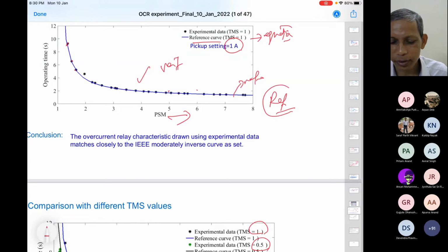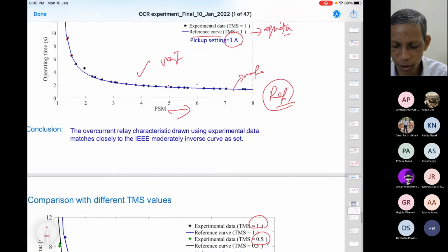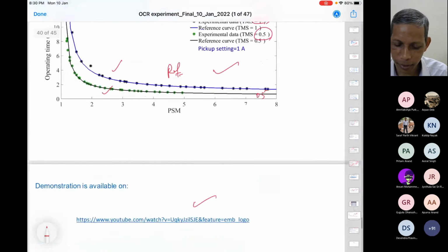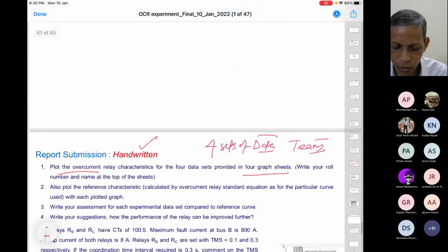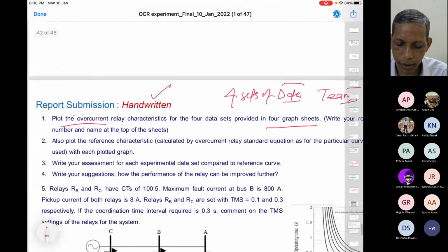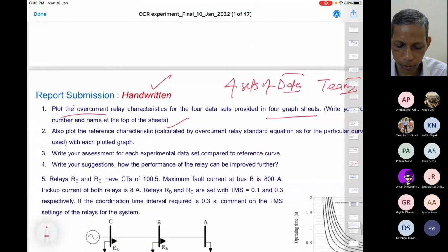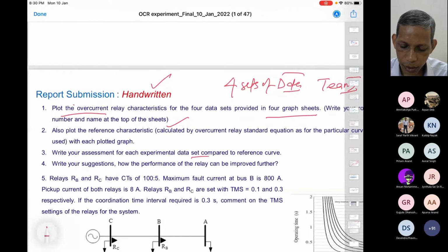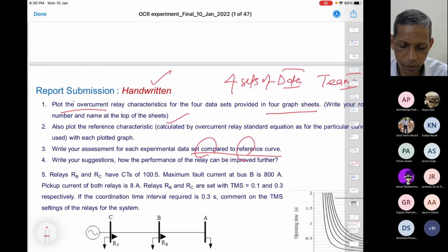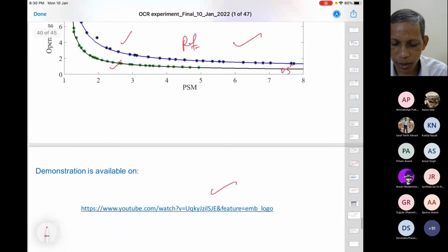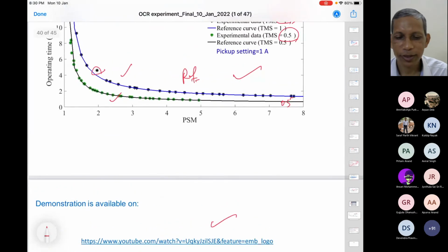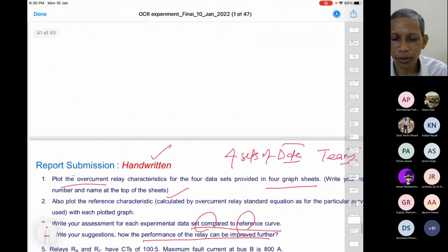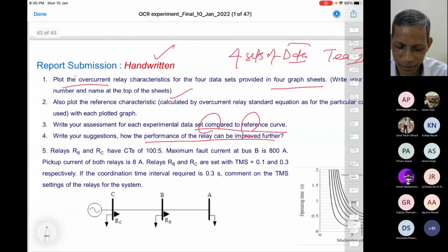Agree? In most of the cases, you'll find that they are following the corresponding curves because the relay is very reliable in that sense. The other one, the reference curve, you have to calculate from that. And then compare the reference curve versus the data obtained. Good, bad limits we have to do. Can there be further improvement, like if you notice some difference here? What may be the cause? You can tell the root cause analysis in terms of that.